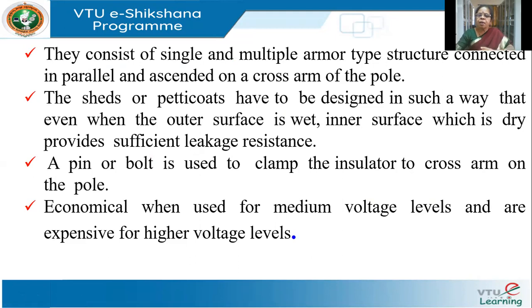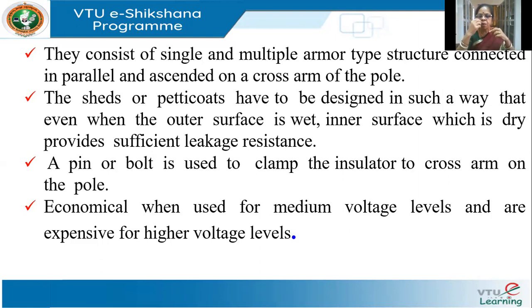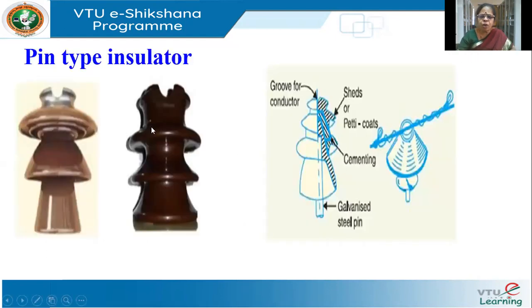The pin insulator consists of single or multiple armor-type structures connected in parallel, and they are mounted on a cross arm of the pole. Why are there petticoats? You can see that these have a bigger diameter, so if there is some water or something falling on it, it will taper off.